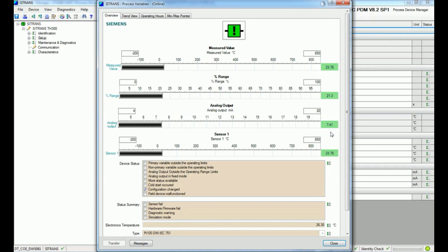By applying heat to this sensor we can see the analog output in milliampere increasing. I will increase the temperature with this sensor and you can see in the analog output milliampere that the current increases and the temperature also increases, as shown in the process variable. The temperature has increased up to 31 degrees Celsius and now it's decreasing, and based on that we get the corresponding analog output.